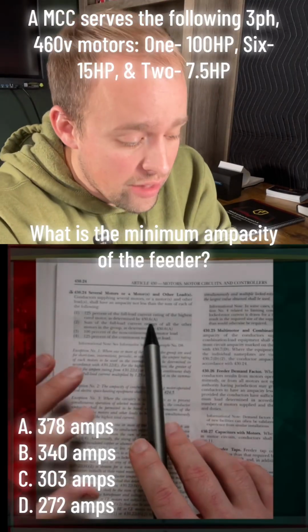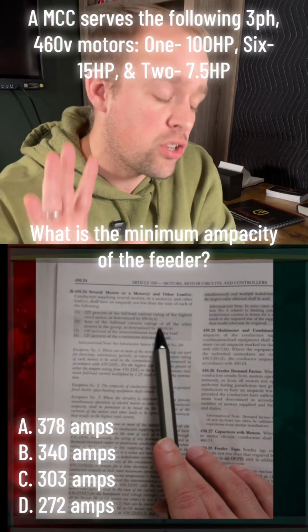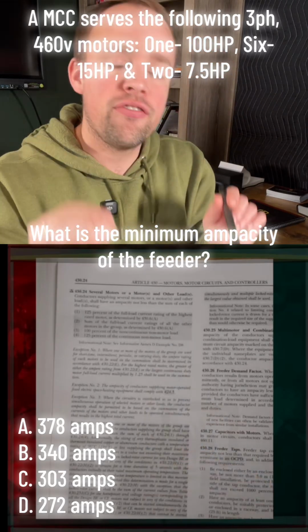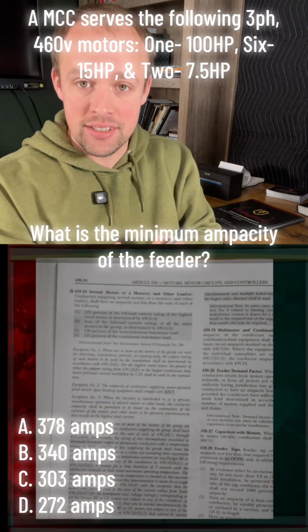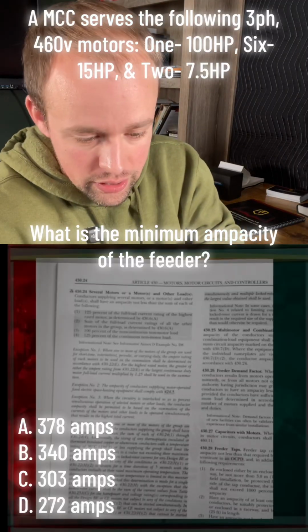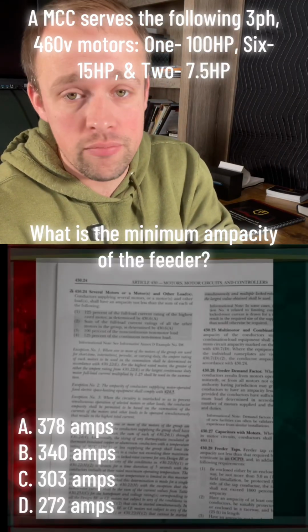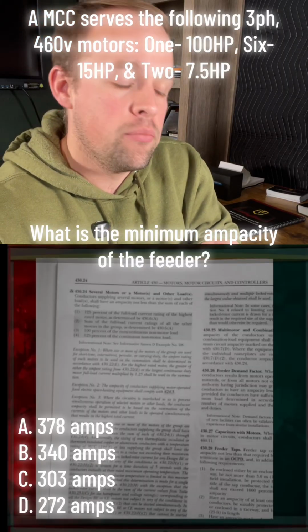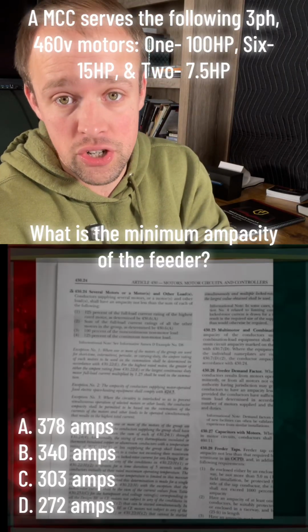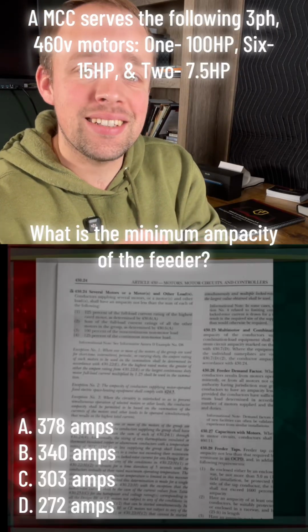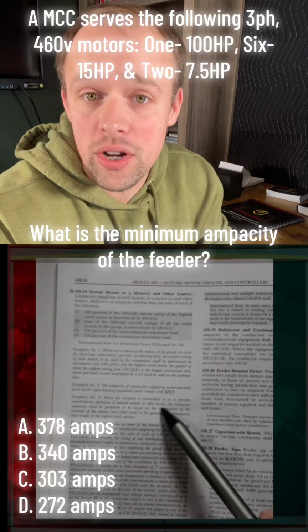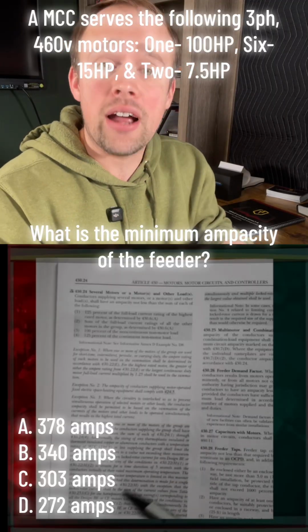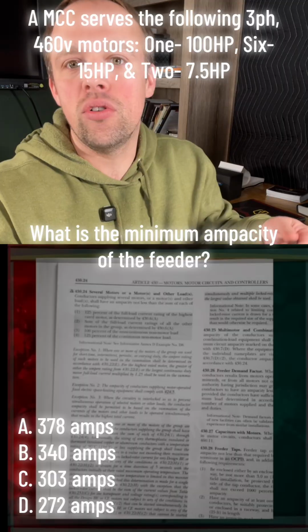So before we do that, let me explain 430.6(A). Again, I encourage you to read that on your own time, but 430.6(A) basically says when we're sizing motor conductors and motor branch circuit short circuit ground fault protection, and motor feeder short circuit ground fault protection, we're going to size it based on the ampacities that the code book gives us. The code book in the back of Article 430 gives us the full load currents.